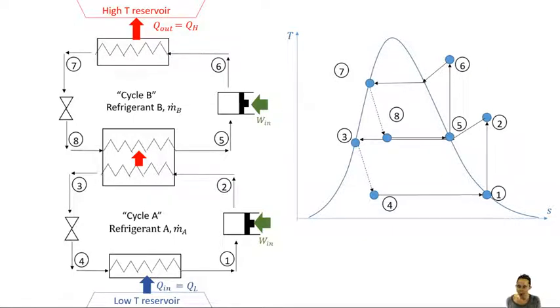Now, when you design your refrigeration cycle, you want the temperature going through that bottom heat exchanger, that evaporator, to be colder than the refrigerated space so that heat flows appropriately. And you need the saturation pressure at that temperature not to be too low.